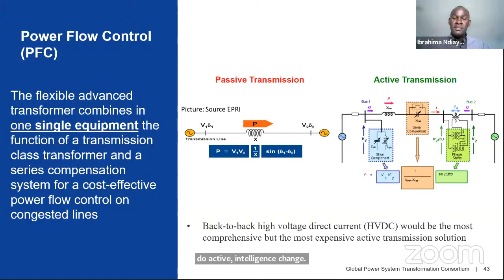This is a picture of the world's first flexible power transformer, developed and designed by Prolec GE and the Advanced Research Center where I belong. This shows a 60 MVA ONAN rated autotransformer with a variable impedance from 4% to 9%. It has been installed and energized since October 2021, operating since then with no sign of failure, installed at a cooperative energy substation in Columbia, Mississippi in the US.